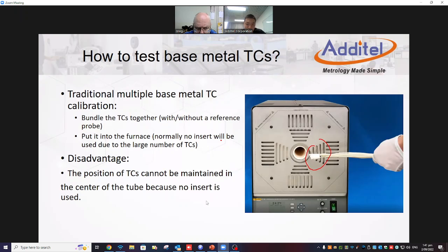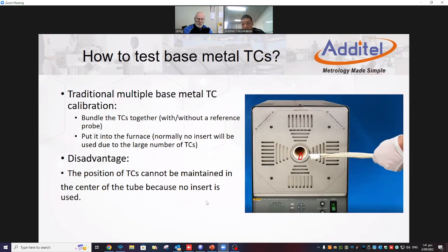But this traditional way gives you a problem. You can see the diameter of this bundle is definitely smaller than the hole, right? So you will see the bundle drop to the bottom of the core like this. That means the center point of the bundle is not on the center point of the core. And this will give you a little bit of temperature difference because of the uniformity. The top of the bundle may have a temperature difference, maybe like 0.3, compared to the bottom one.